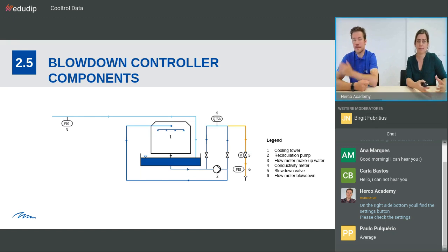Now we show you really parts of the blowdown controller. First of all, in order to control the blowdown or the bleed off, we need a parameter. We use conductivity in this case because it's easier to measure than total dissolved solids, and we want an online measurement, obviously. We have a bypass line from the recirculation pump going out on the pressure side of the recirculation pump and coming back on the suction side. Since there is a pressure drop over this bypass line, we ensure that there's always enough flow so that the measurement is really correct and we don't measure in stagnant water. The measurement is shown here with the number 4, quality measurement, conductivity.